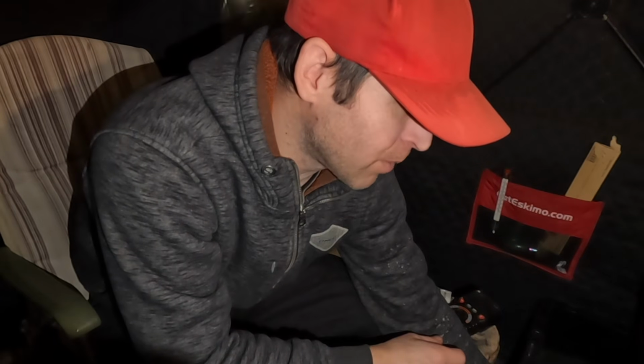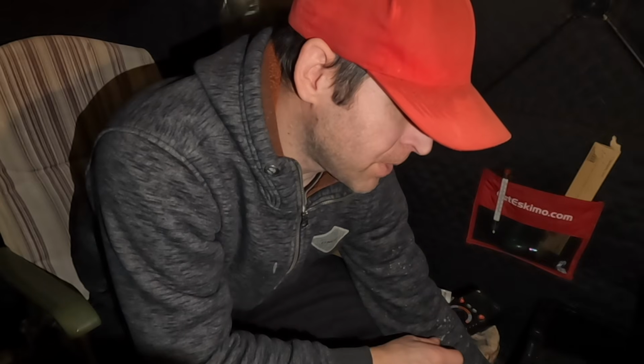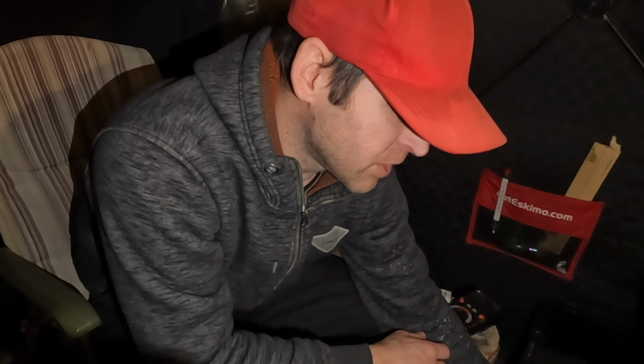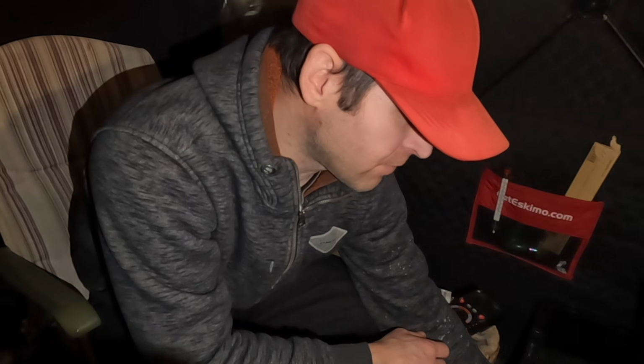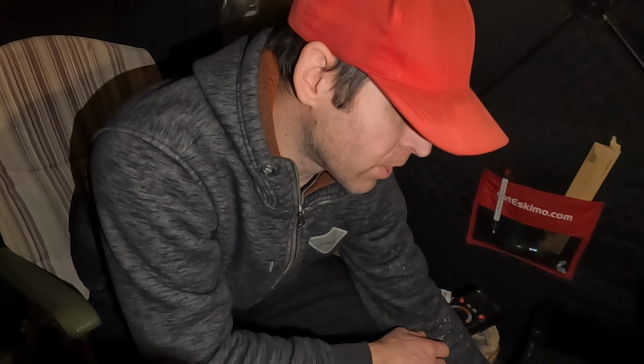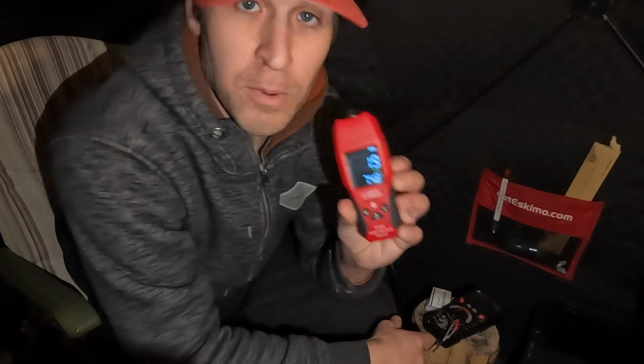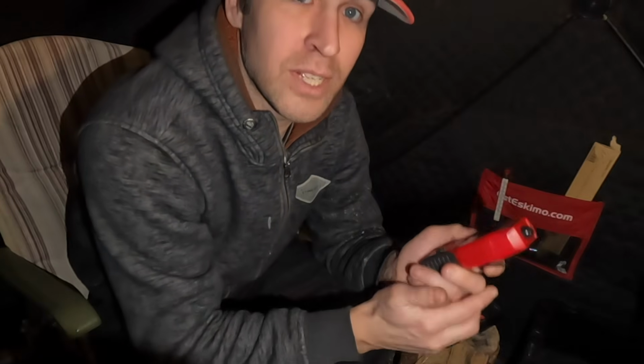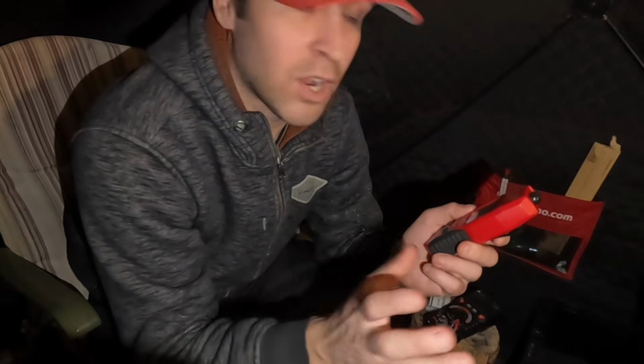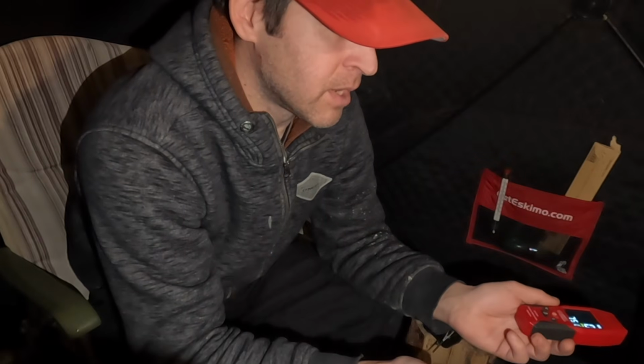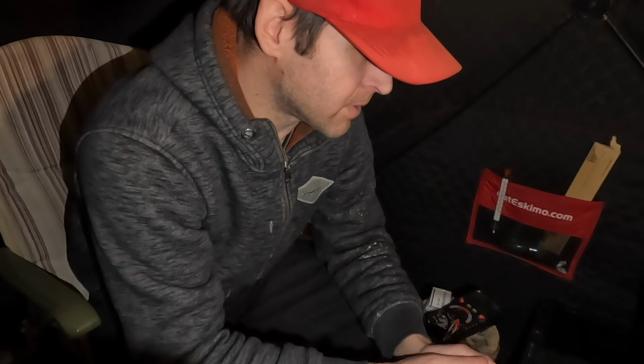The exhaust, I pulled the pipe off and measured the carbon monoxide, and I'm actually shocked. I thought it was going to be much higher now that we're pulling heat out of it, but it appears it is actually between, I checked it earlier off camera and it was about 20. Now we're between 18 and 20 parts per million, which is really impressive. That means that running through this system isn't going to cause any kind of sooting or carbon issues inside of the burn chamber. I mean, try it at your own risk, of course, but yeah, I don't foresee any problems.